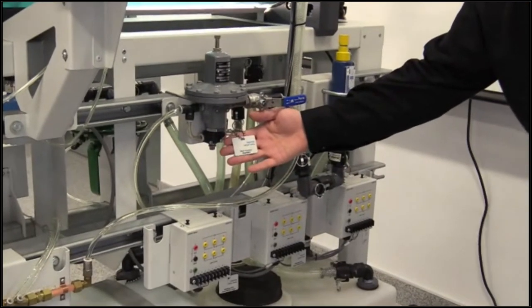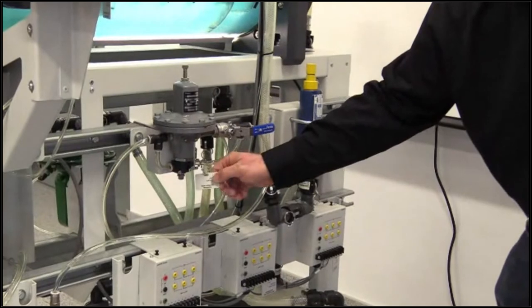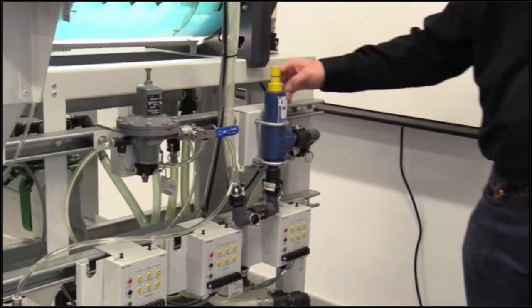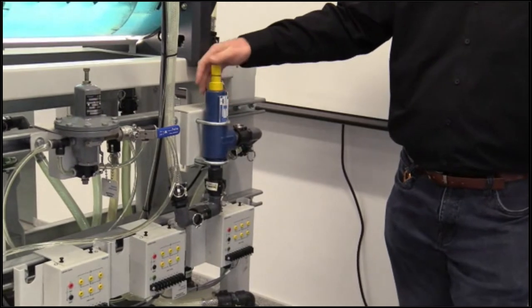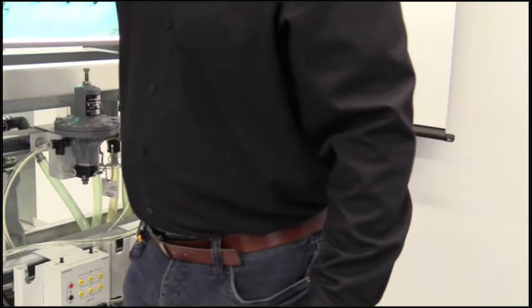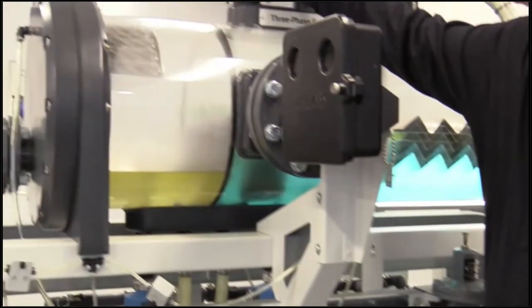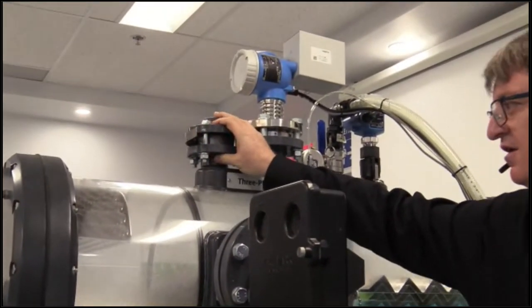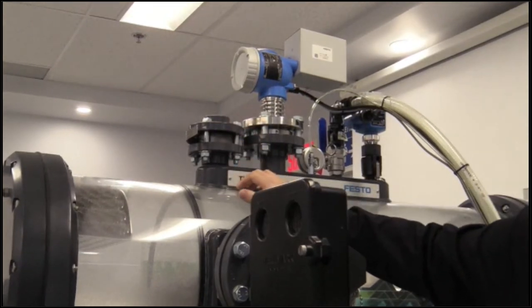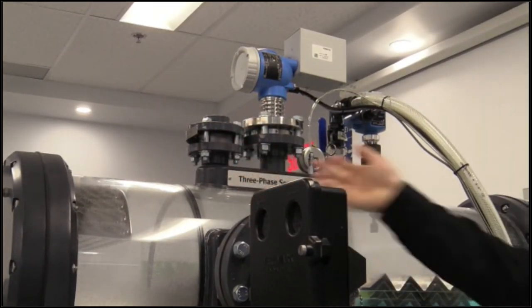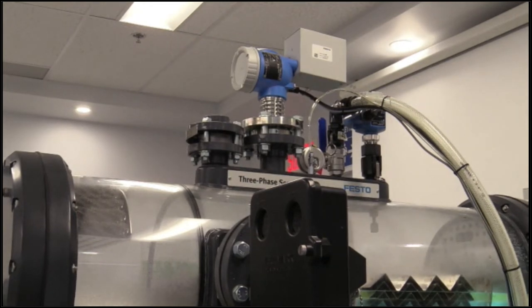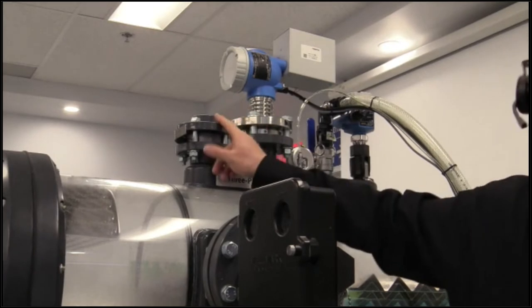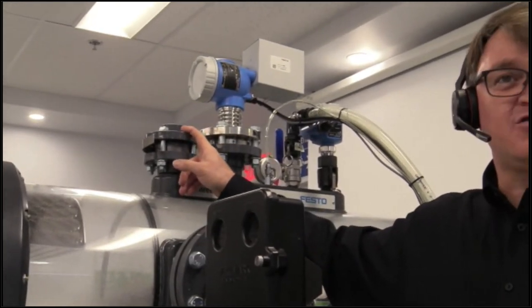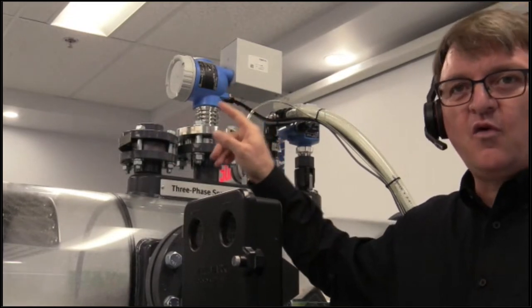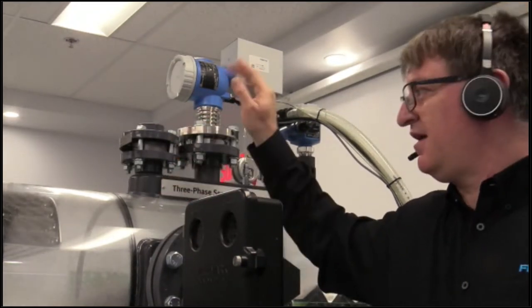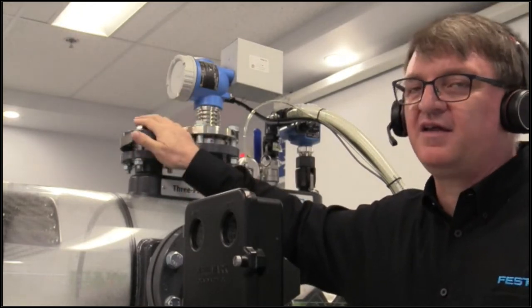Here we have a back pressure regulator. All the devices have these plates that tell you the names. Here we have a safety valve for the pressure. And also here we have this disc. This is the burst disc. So when the pressure arrives at a certain level that we consider the maximum limit, and let's say this valve fails and something else fails, this one is just going to blow. So it's like placing a mechanical fuse. We're creating a known weakness in the system. So if there's a problem, we know and we want it here.